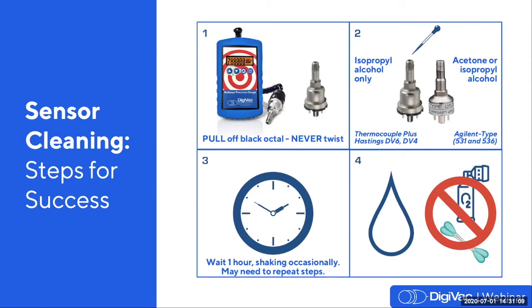Take your sensor, position it flange or threads facing up, and find the appropriate solvent for the process. For the Thermocouple Plus sensors, as well as the Hastings DV6 and DV4 models, isopropyl alcohol only should be used in the sensor, as the top is a plastic component. For the fully welded stainless steel sensors, such as the Agilent 531 and 536, you may use isopropyl alcohol, or you may also use acetone. Acetone would melt the plastic in the Thermocouple Plus and DV6 and DV4 sensors, so we reserve that only for the fully welded stainless steel.